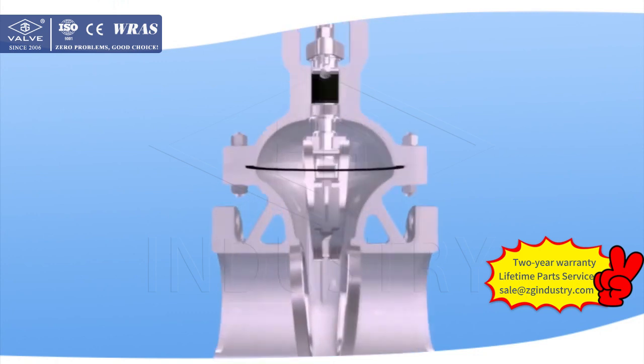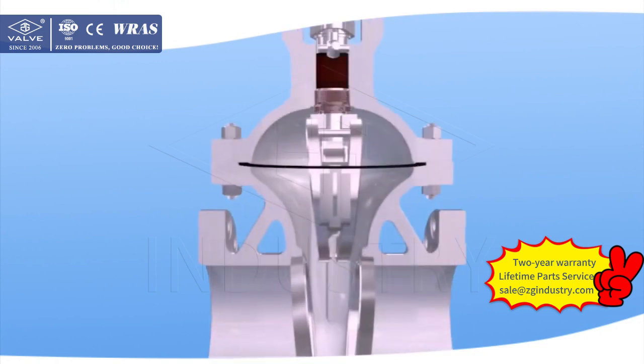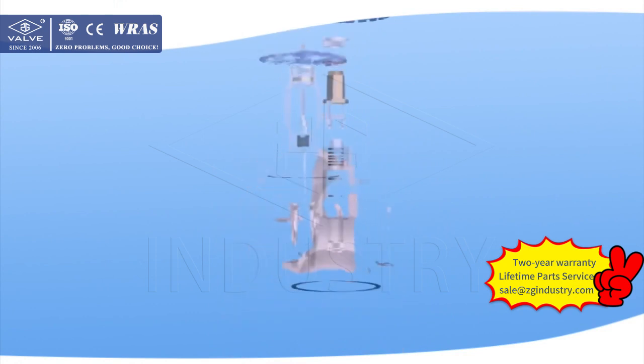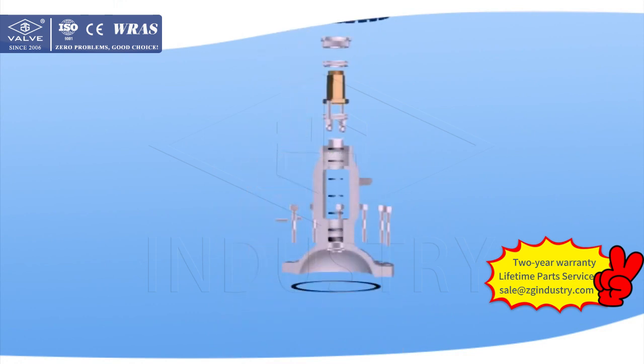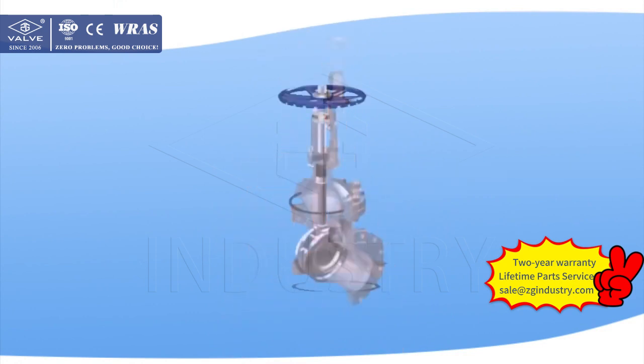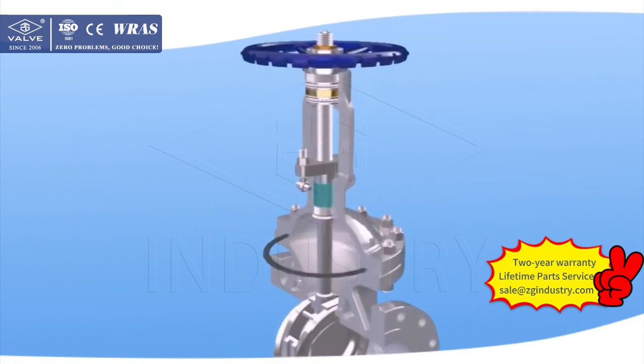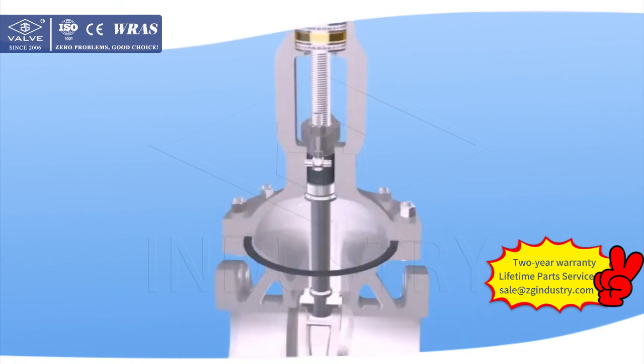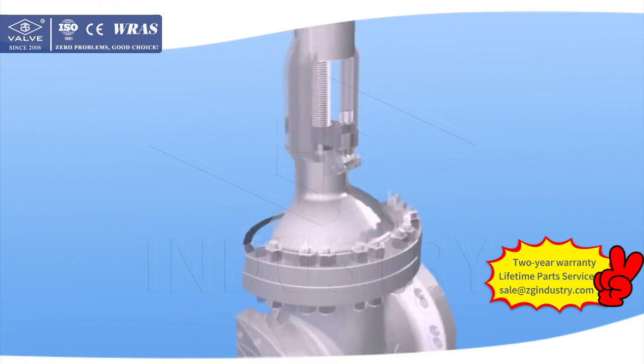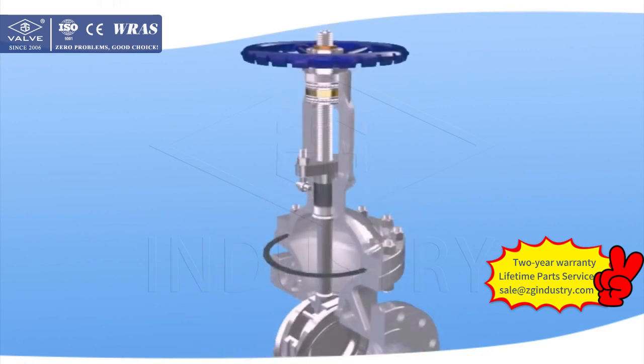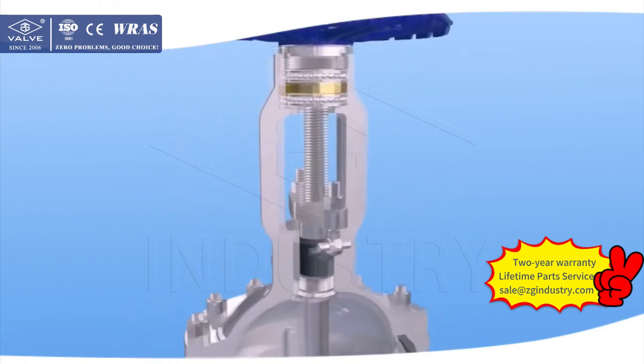4. Back seat design will protect the packing when the valve is fully open. Packing is flexible graphite, with good sealing capacity, and a venting system is also available. Packing bush and gland are bolt structure. Pressure process will enable the stem to automatically centralize, avoiding stem sticking.